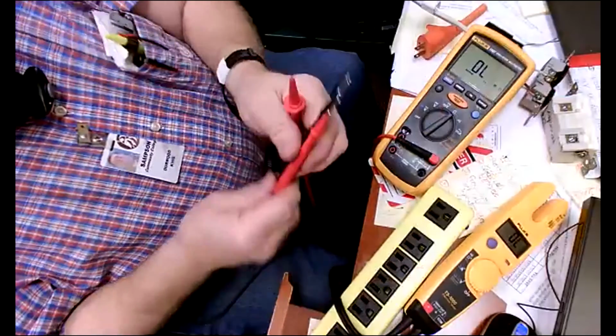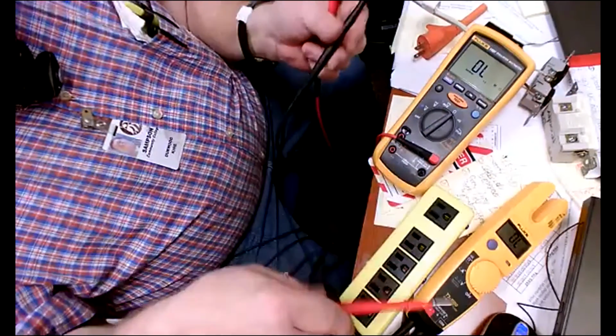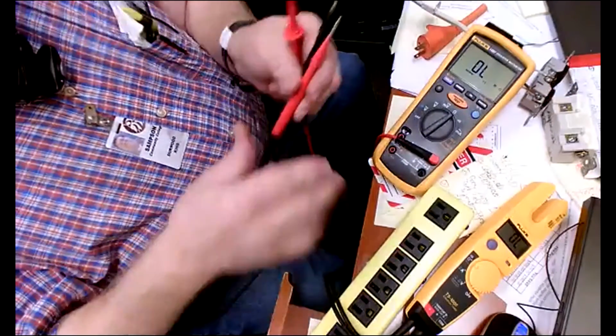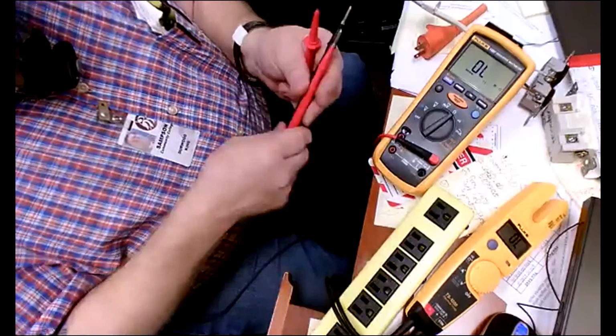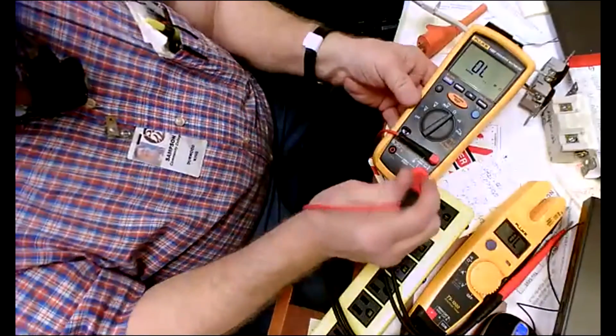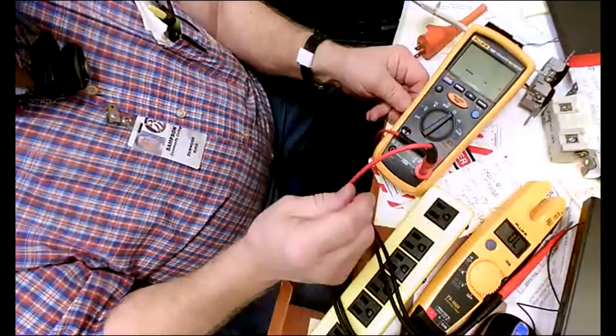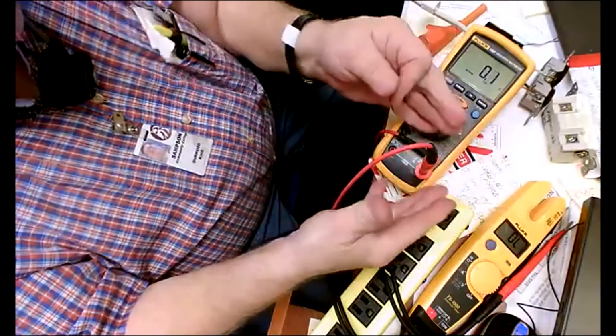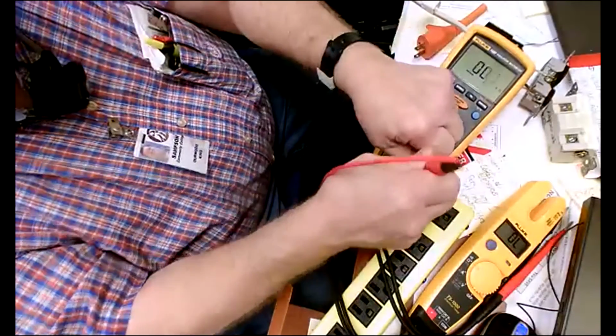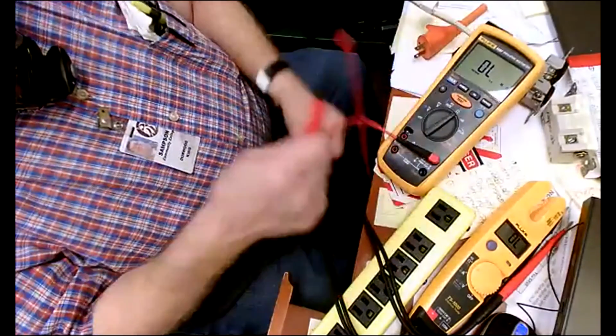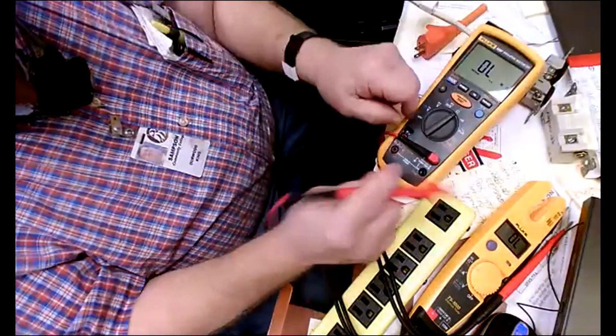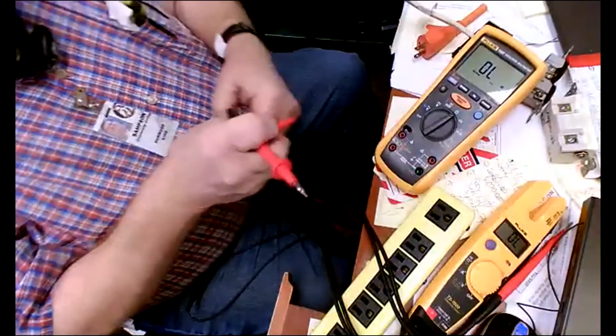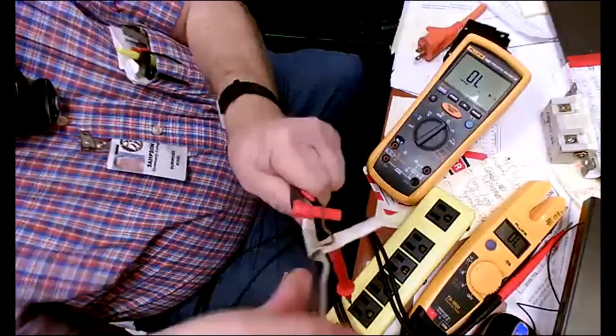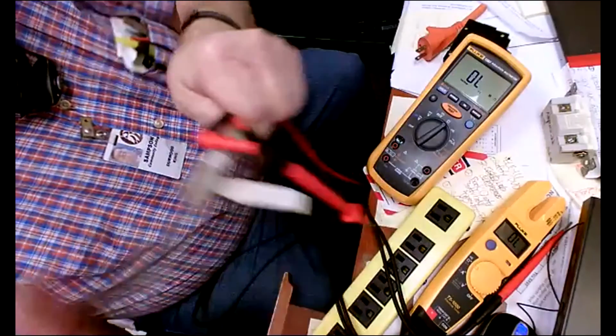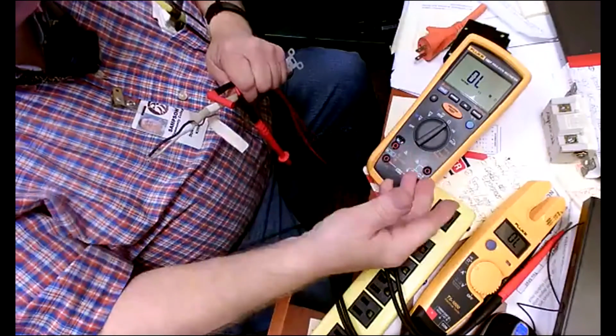But you could still do a loop test for each wire once you get the meter apart, and see which lead it is. My point here is, if you do this and it's not good, and you do the same thing with the black test lead and they both read bad, then you might want to take a piece of solid ground wire, a piece of bare wire like this, and go jack to jack and see if it's the meter.